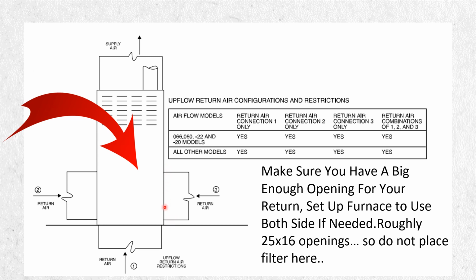If you put a filter here, then you restrict that down to a 2.5-ton system. So if you have a 5-ton system and you put a 25 by 16 filter here, you have choked down your 5-ton system to a 2.5-ton. So if you're going to do that, you have to use the other side or come out of the bottom. You could actually put this up on a plenum and turn it upside down here and then put a filter here and a filter here. That would work. But you cannot filter here. If you do, you're going to have to come out both sides or the bottom. So just keep that in mind.